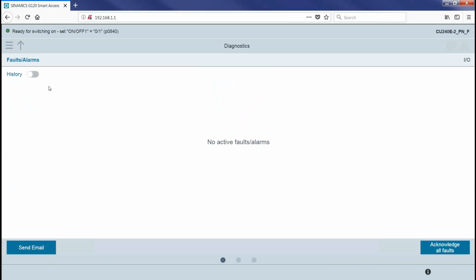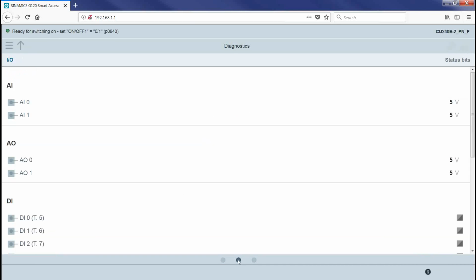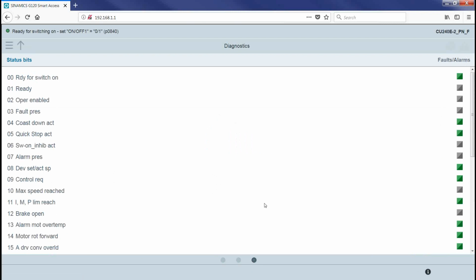Diagnostics, again, if we had faults, I can go back to history. But again, no active faults. If there were faults, you can acknowledge here the same. Again, send email if you've got a mobile device. You can click that and send an email of what the actual fault log is if you need to. Again, the other two pages are analog and digital inputs and outputs. Good monitoring tool or troubleshooting tool if you need. And then the same status bits.